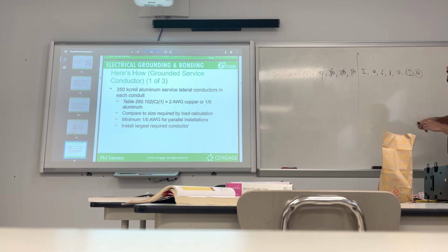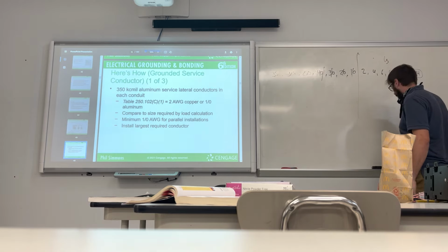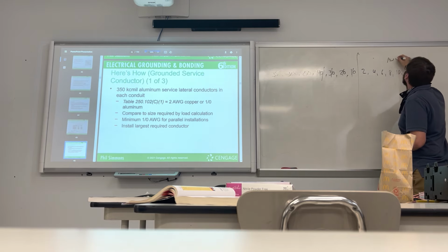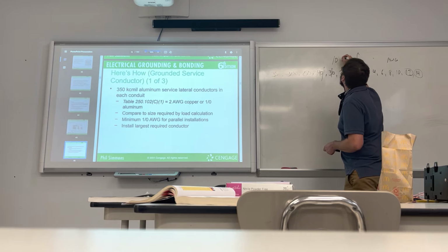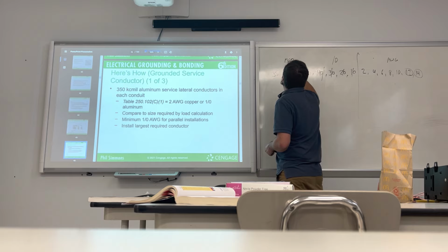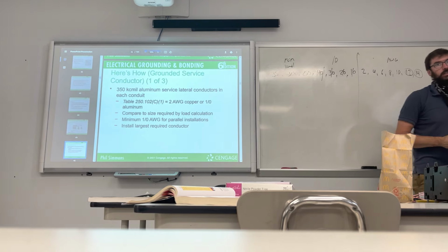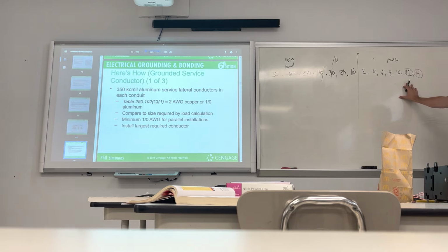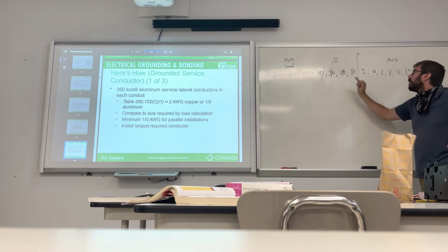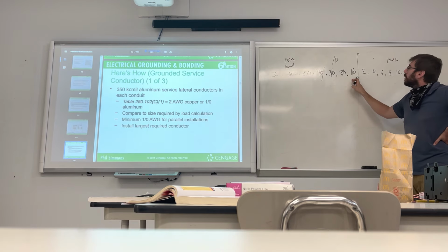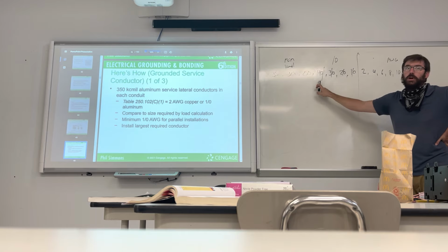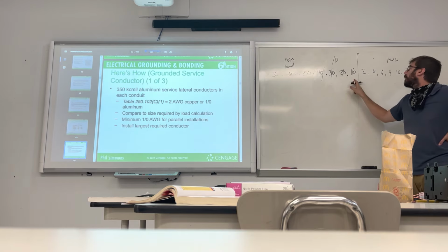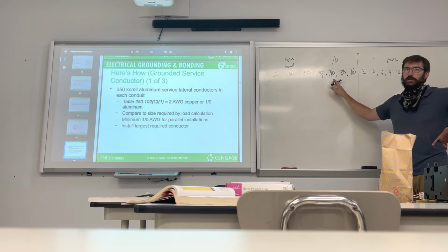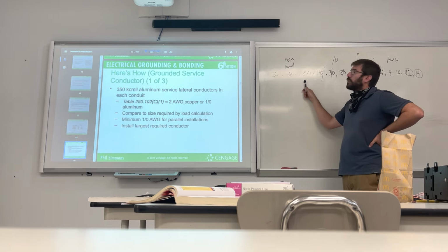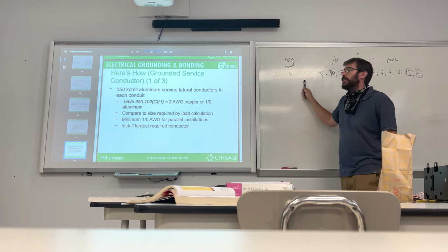So like I said, when we're talking gauge, this is AWG. This is aught. This is MCM in my day, or now it's kcmil. It was MCM for a long time, and they switched to kcmil. But AWG or gauge, the smaller the number, the bigger the wire, right? Right here at the aught line, it switches between 2 and 1. So now this only lasts for 4. So it goes 1 aught, 2 aught, 3 aught, 4 aught. As those numbers get bigger, 1 aught can carry less current than 2 aught, 2 aught can carry less current than 3 aught, and so on and so forth. And then once we get past 4 aught, we start getting into kcmil or MCM.